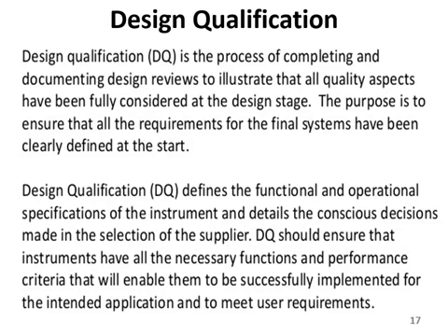So DQ or design qualification is actually the functional and the operational specifications of the instrument and details regarding the conscious decisions made in the selection of the supplier. DQ should ensure that the instrument has all the necessary functions and the criteria that is going to enable you and the machine to be successfully going through the system and going to implement all the requirements and the needs of the user.